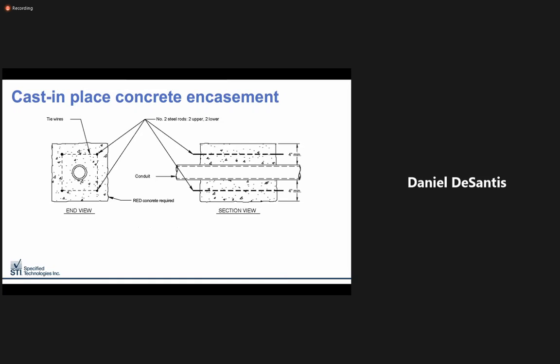Let's have a closer look at cast-in-place concrete as a protective enclosure. While concrete makes an excellent fire-rated barrier for vertical and horizontal separations like walls and floors, it lacks the versatility to provide reliable conduit enclosure due to its difficulty to visually inspect once set. And once it is set, making adds, moves, and changes is virtually impossible. This is a problem for the life cycle of a building, as upgrades and changes in technology are a way of life in modern construction.